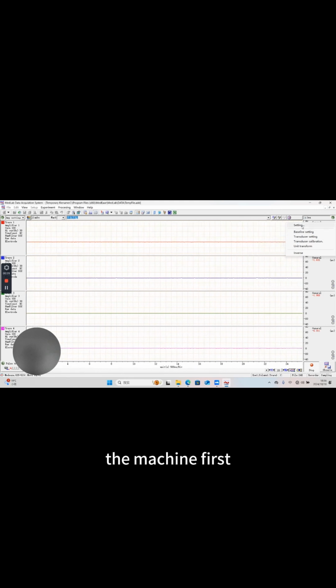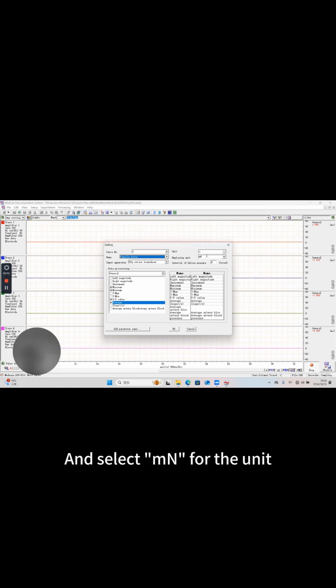The current mode is General, and we need to change the mode to Tension Sensor first. Click Setting in the upper right corner. Remember, this must be set after running the machine first. General needs to be modified here. Click. Select the second item, Tension Force, and select mN for the unit. Then select the first General here, and after confirmation, click OK.